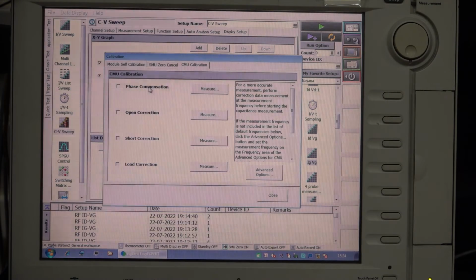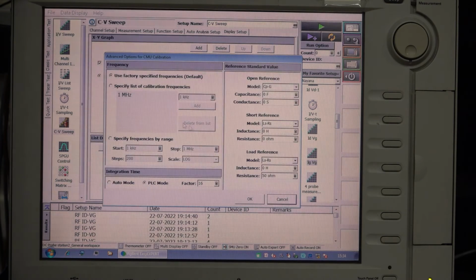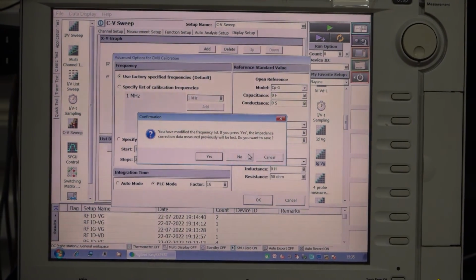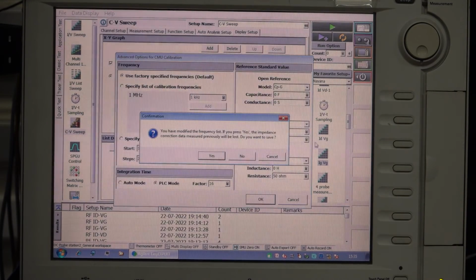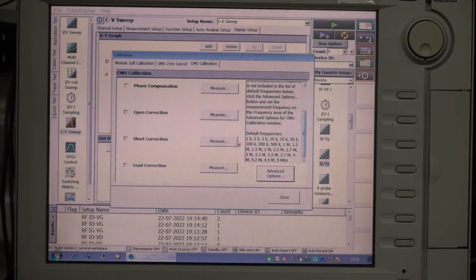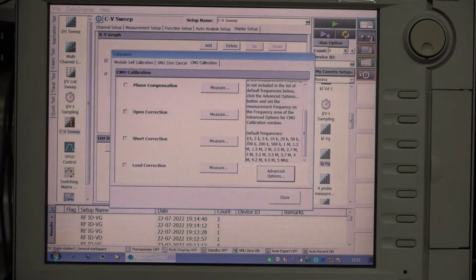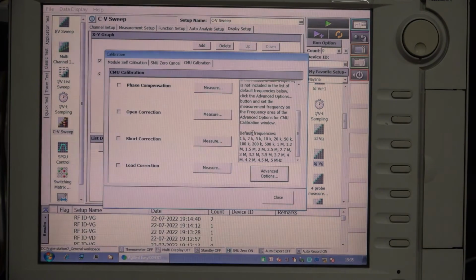Here we can do a phase compensation. In the advanced option we have the use factory specified frequencies option. That means the instrument will have the desired frequencies for the calibration. We can use this default calibration frequency range, or you can use a custom frequency range according to the measurement requirement. Now I am using the factory specified frequencies, which are these listed here. That means I can cover 1 kilohertz to 5 megahertz. The entire frequency range will be covered during my measurement.